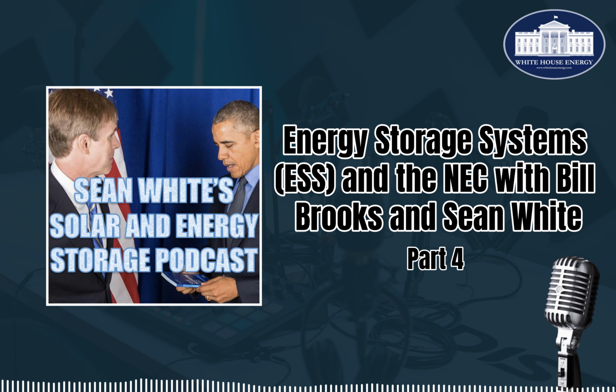This is just saying, hey, if we're already going through an engineer to add a source or a load, show the calculations and show that everything's fine. So there's no 120% rule on switchgear or anything like that. It's just whatever the calculations come out to be, as long as it doesn't overcurrent the equipment, you're good to go. Good to go. All right.